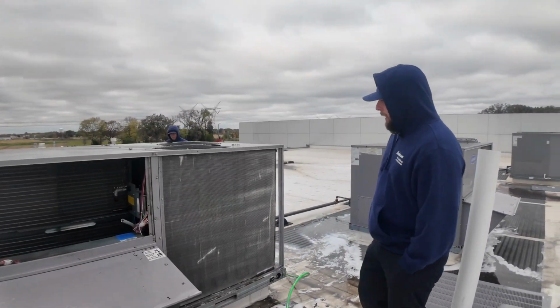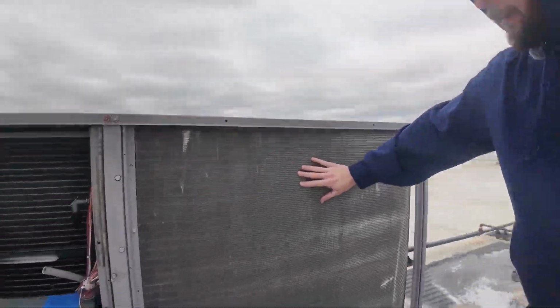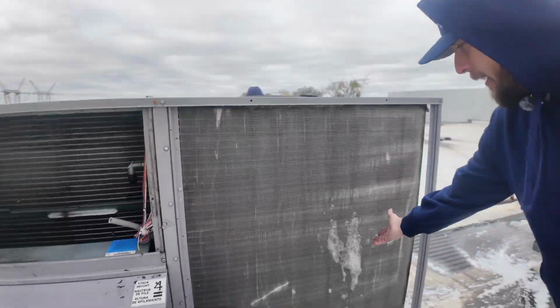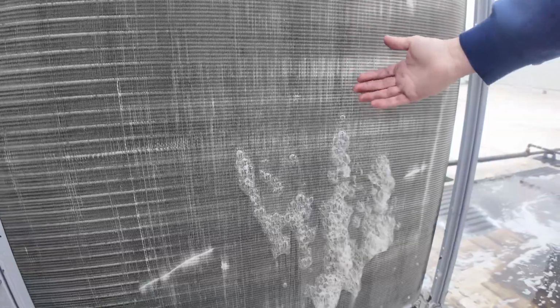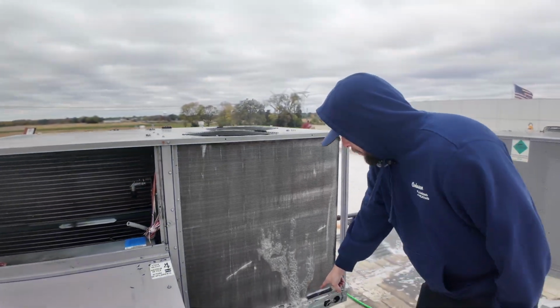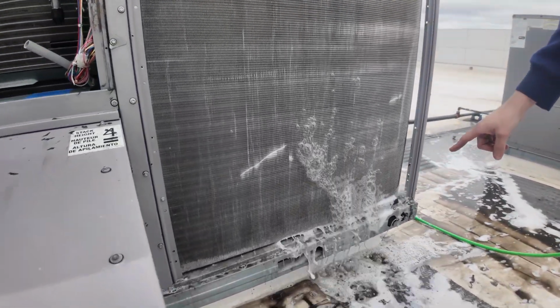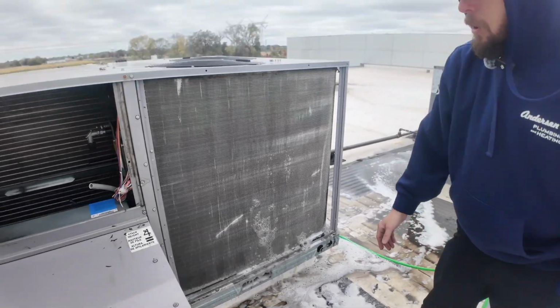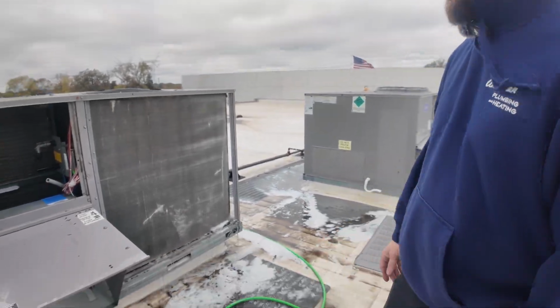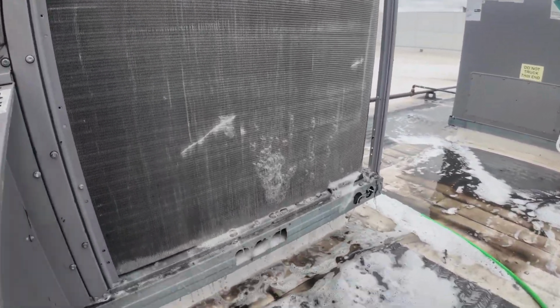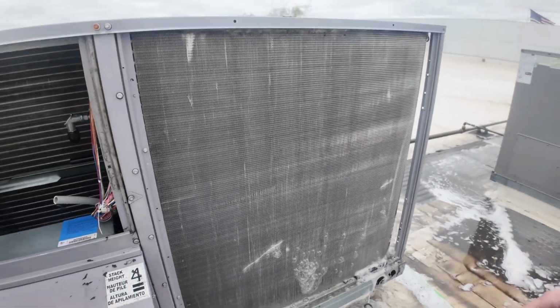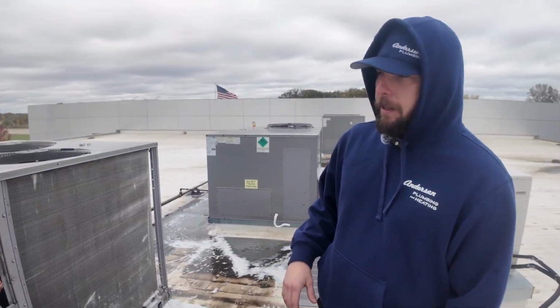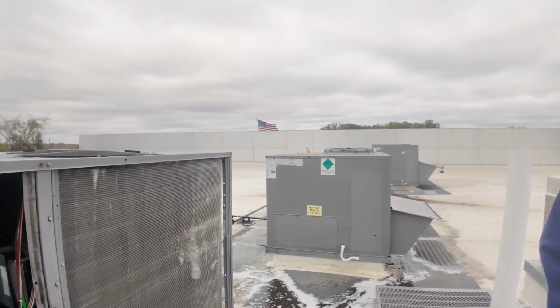All right, so what Cory's doing now, this is that coil that we showed you before that was completely disgusting and packed. You see the bubbles coming through. He's washing it from the inside out. So if you look at all that dirt and nasty water that's just rolling out of these coils, those are all the things that reduce your efficiency as the year goes on, without the proper maintenance. So this is the last step in the process. We get in there, pressure wash everything, get all the dirt and debris out of the coil, rinse all the coil cleaner through the unit, and then we put the thing back together. And that's how we make it another 6 months, hopefully with no breakdowns.